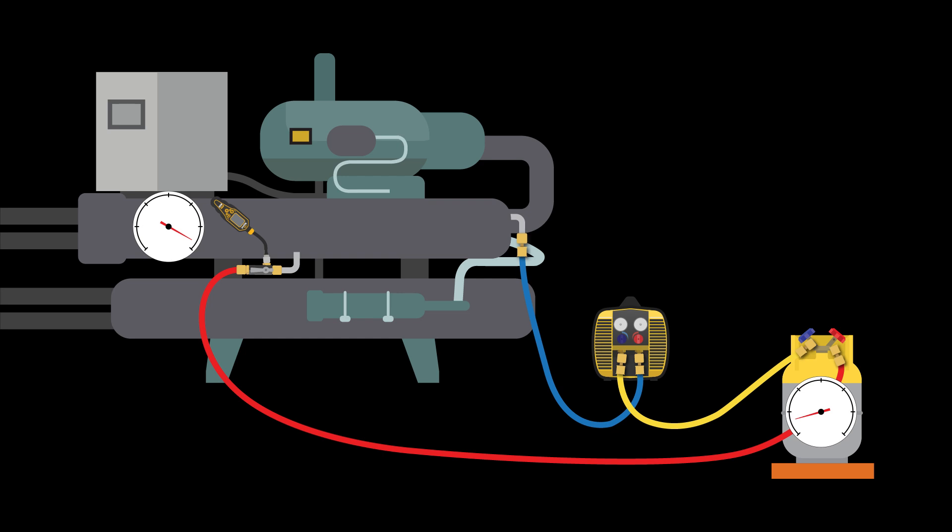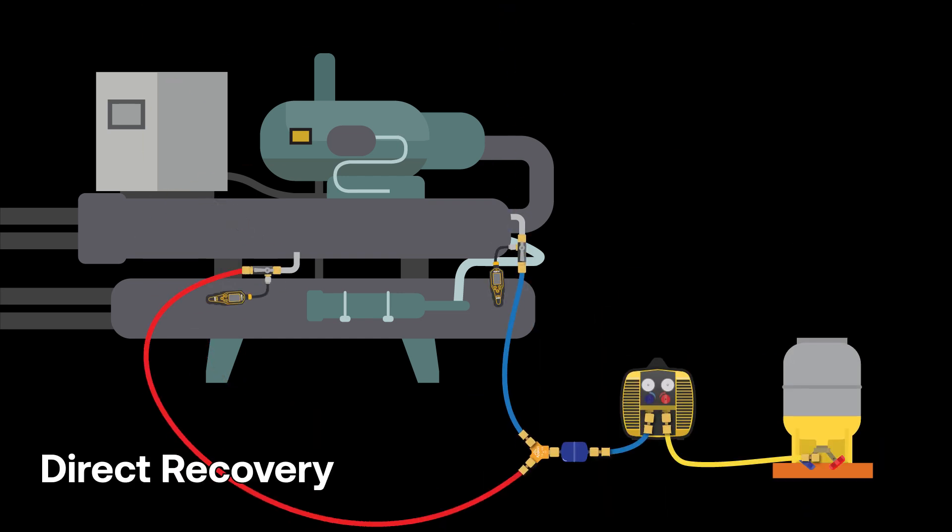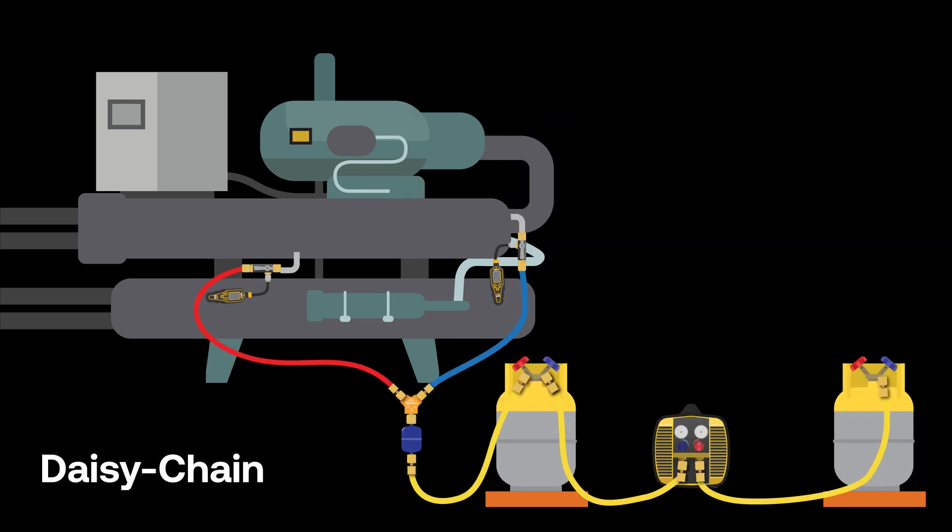The drawback to this closed-loop setup is that you will have to stop the process and switch to a direct refrigerant recovery setup to remove any remaining vapor. Since push-pull has to be stopped and reverted to a direct refrigerant recovery setup, sometimes it is preferred to use daisy-chain recovery on larger systems.